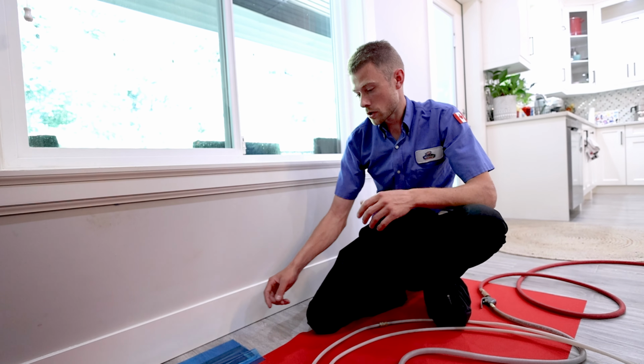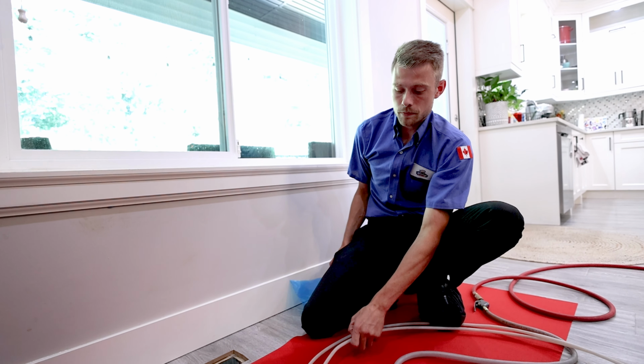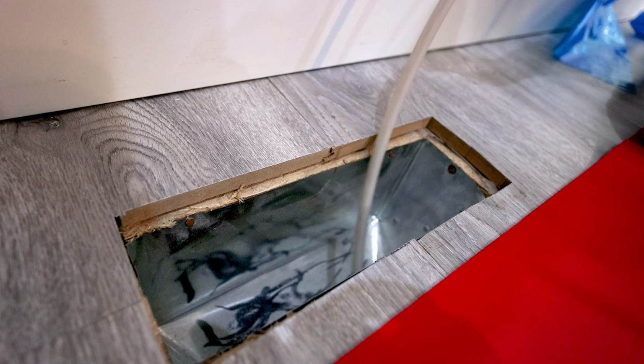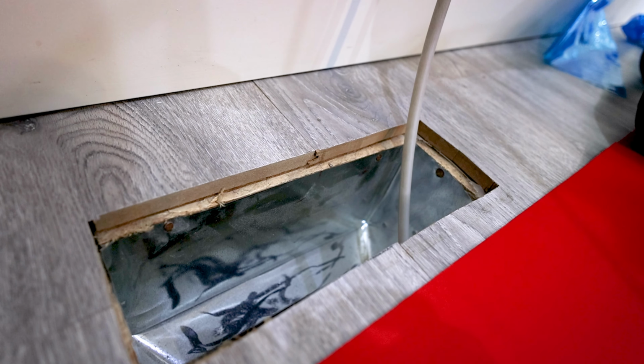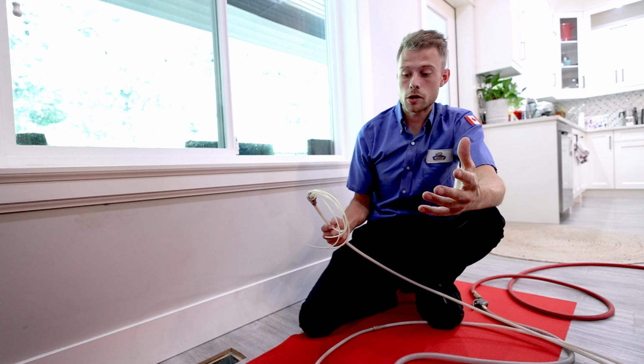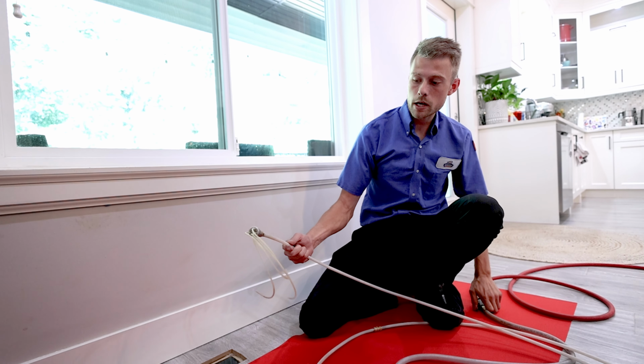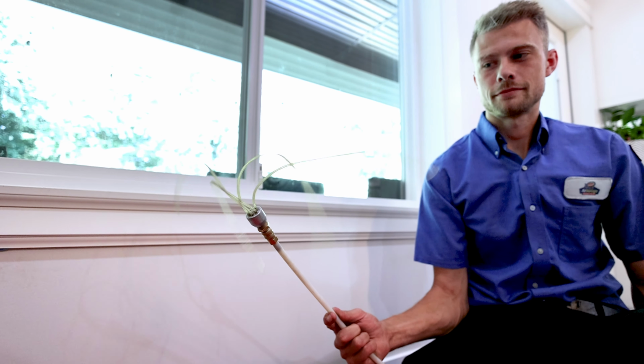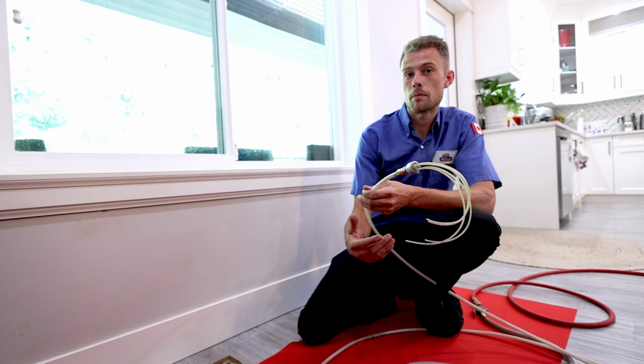Once we get to the ductwork, we have our compressed air here. This acts as a device that basically goes through the ductwork and whips it as it pushes all the dirt and debris. So if I give it a little bit of air here, as you can see, that's going to move all that dirt and debris towards our HEPA grade vacuum.